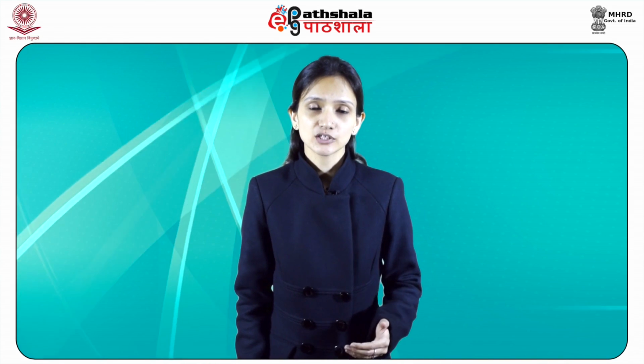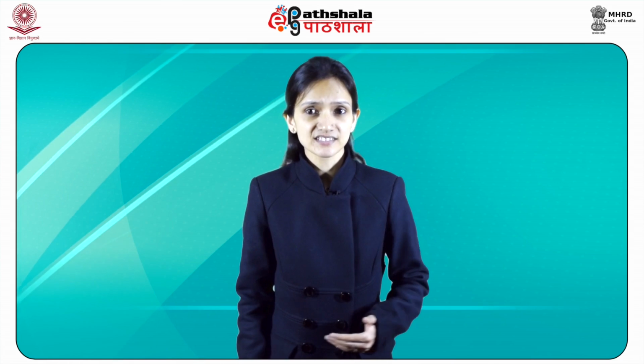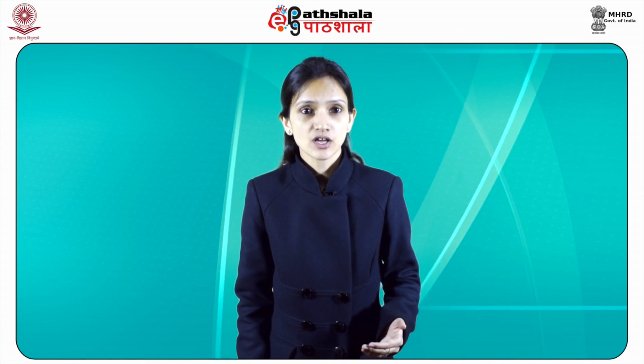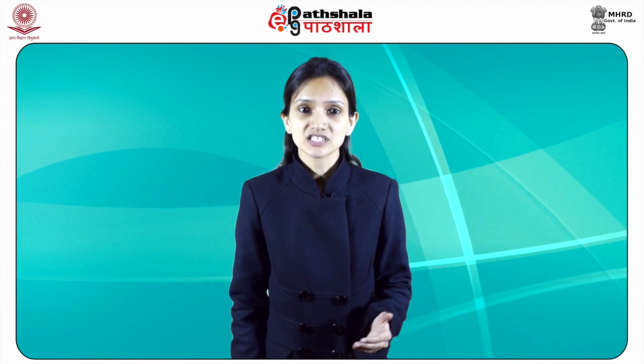Next is sensitivity and detection limit. A number of parameters, including the S/N ratio, affect the sensitivity of a particular instrumental method. Physical and chemical properties of the analyte, the response of the input transducer to the analyte, and the contents of the sample matrix are some of the more important factors that determine sensitivity. Sensitivity is defined as the ratio of the change in the instrument response, that is IO, output signal, to the corresponding change in the stimulus, that is C, concentration of the analyte. Slopes of calibration curves are used to determine the sensitivity values.